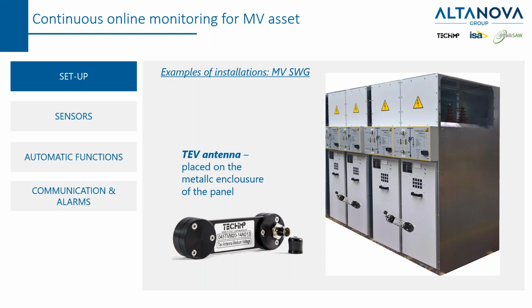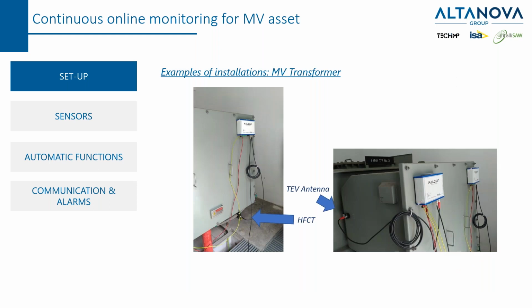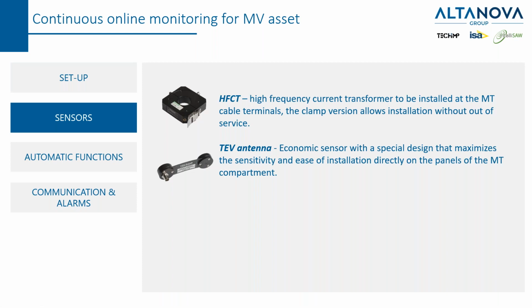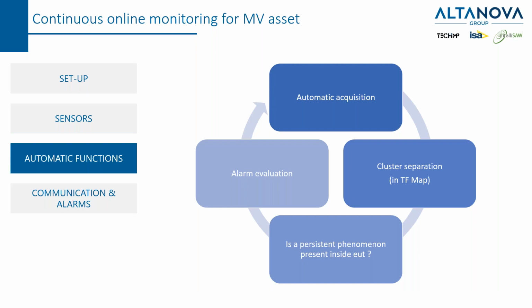Another setup is to use the TEV antenna placed on the metal enclosure of the panel. And this highlights again that this technology is totally non-intrusive. Regarding the sensor, here is some example of installation also on the medium voltage transformer. You can see here the HFCT on this ground connection and the TEV in this part. Of course, the TEV has to be placed in the part of the compartment that is not shielded. Basically, the 2 sensors I already mentioned: the typical application is the high frequency current transformer installed on the medium voltage cable termination, and the TEV antenna directly on the enclosure.